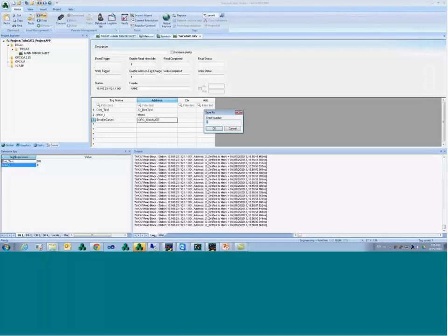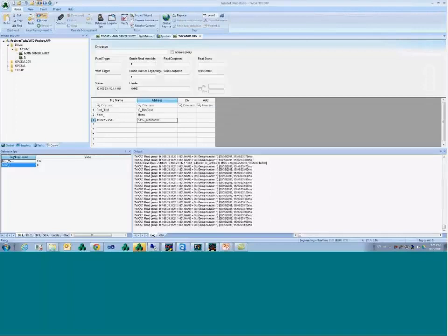All right, I'm going to save this. As soon as I save, you can see how fast the communication is happening now. If I pause for the group 1, which is this worksheet here, as you can see, sometimes I have even less than 30 milliseconds between messages. Sometimes a little bit over that, like here, almost 40 milliseconds, but that's pretty much what you're going to have. Here I have, again, less than 30 milliseconds.